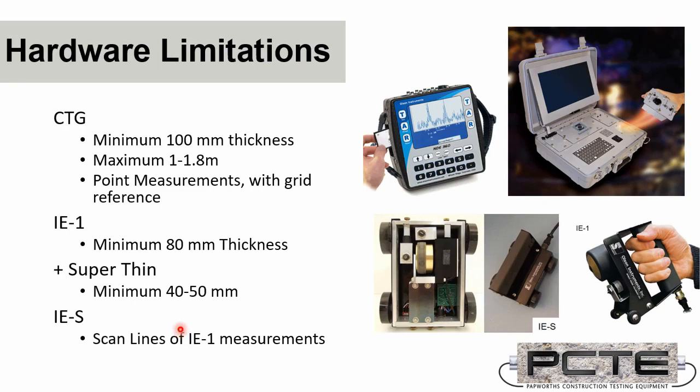There's also a scanning system, the impact echo scanner, which allows, rather than point measurements, a line of measurement to be taken. So if you need very fast productivity, you need to cover entire floor sections or entire wall sections very quickly, 100% scanning, then the impact echo scanner would be a useful improvement.